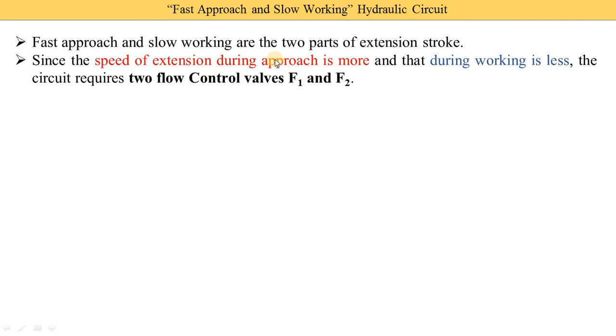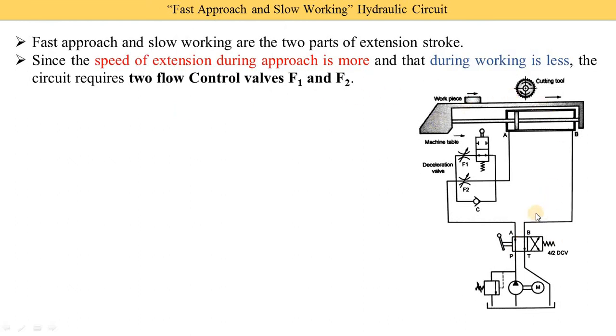One control valve is called F1 and the second is called F2. The speed during extension in the approach phase is high, and during working it is less. This circuit requires two flow control valves, F1 and F2, installed between the directional control valve and the machine component. The machine component includes a cutting tool, a table, and a workpiece on the table, which moves via a double-acting rodless cylinder. A higher speed is required during the fast approach, and slow speed is required once the workpiece and cutting tool come into contact.